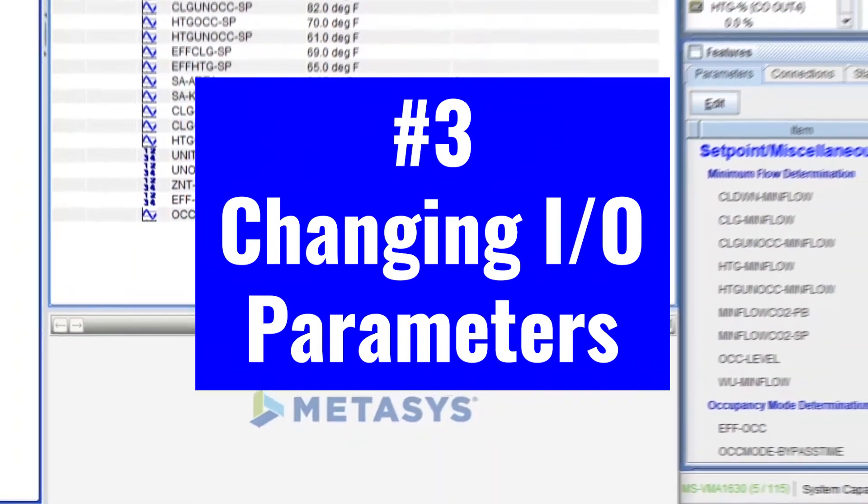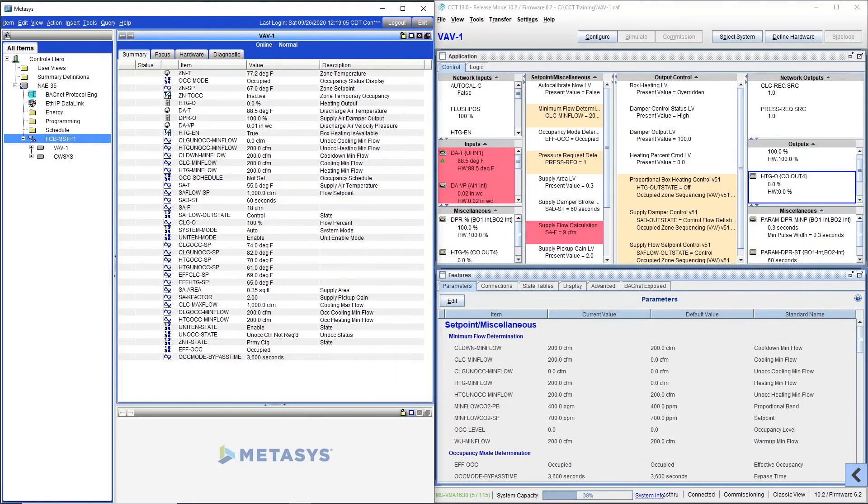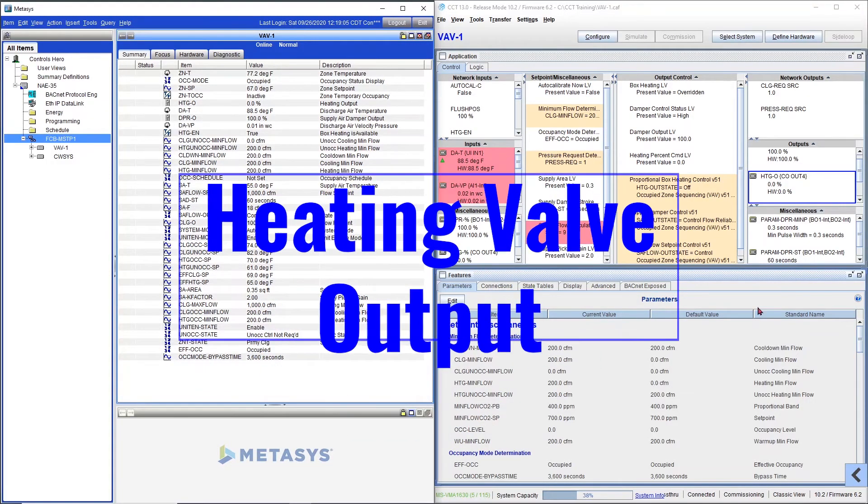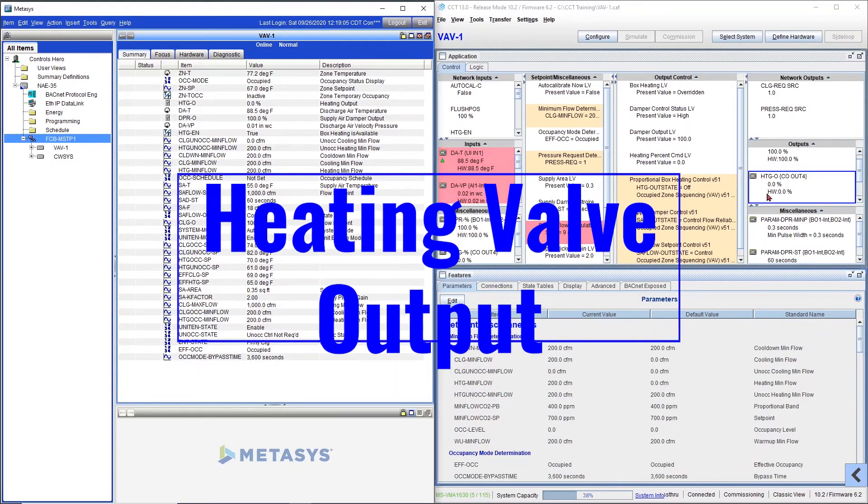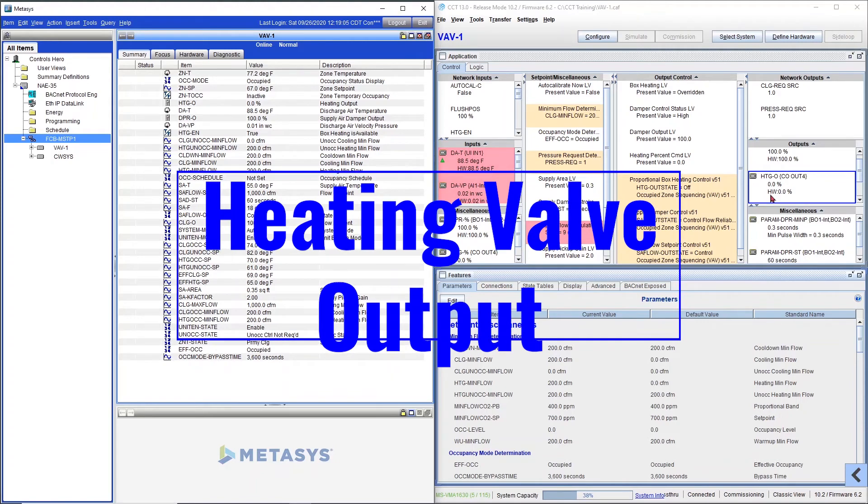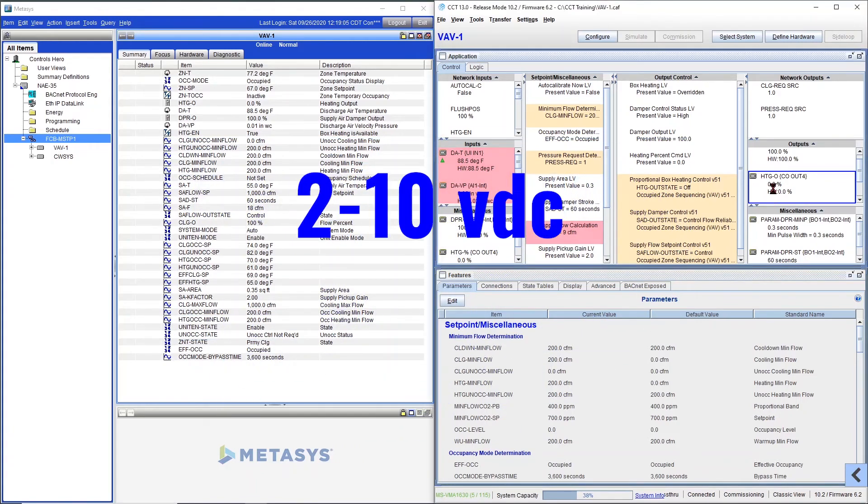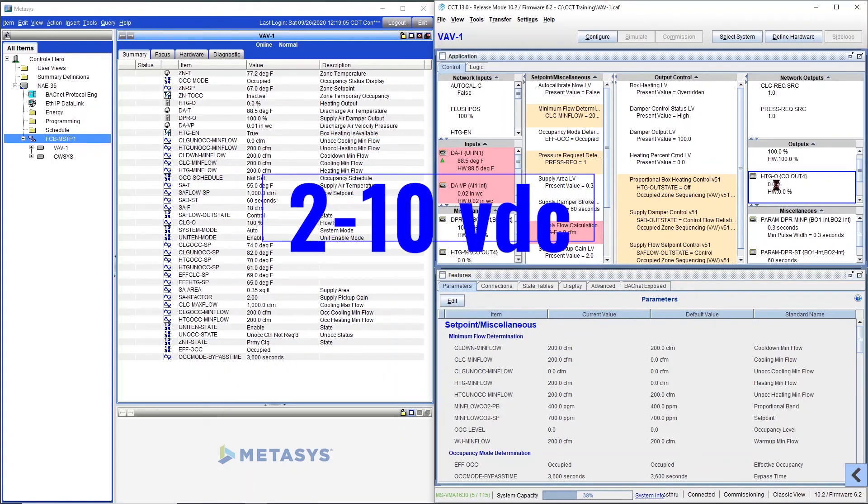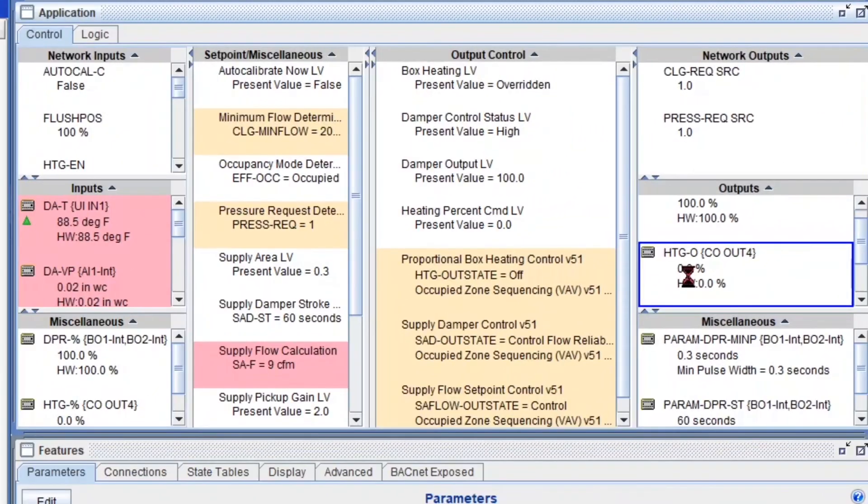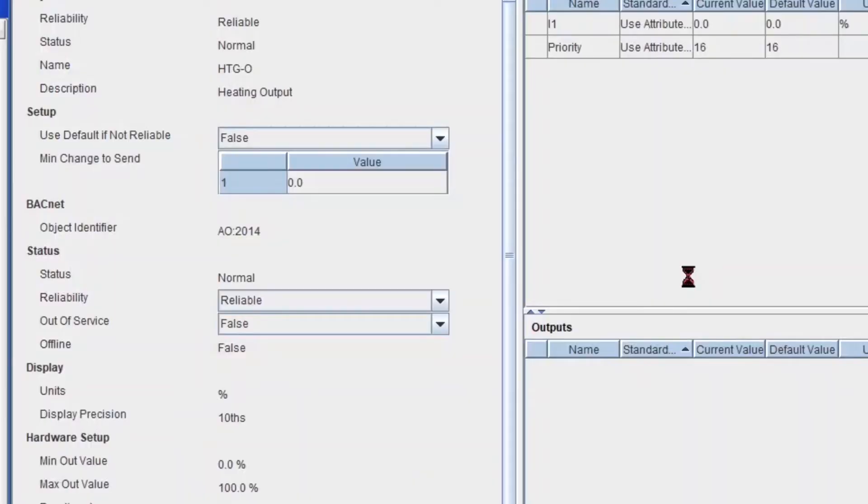Now for my last trick, changing input and output parameters from Metasys, I'm going to start with a quick and easy one to follow. A heating valve output. And let's see that we have a 2 to 10 volts DC Belimo valve. But we made the mistake of not setting it as a 2 to 10, but instead we set it as a 0 to 10 volts. So let's see.